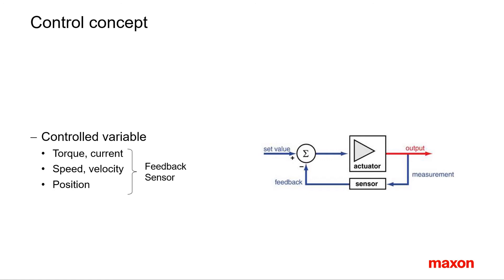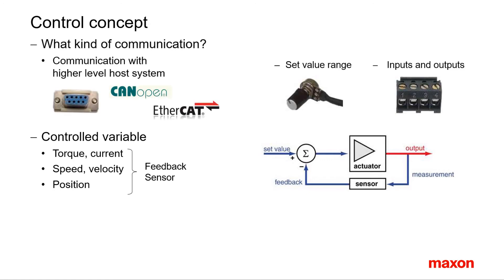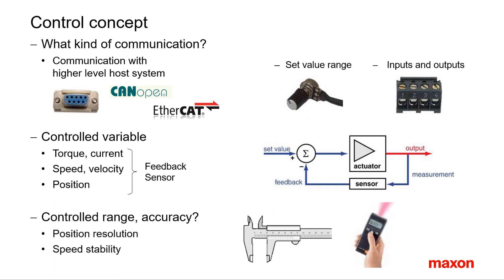Are there additional sensors needed? How is the information passed on to the drive system? Is there a supervisor or master system? If yes, how does this higher-level host system communicate with the drive — for example, via CANopen or another fieldbus, or via a serial interface such as RS-232 or USB? Set values could also simply be given as a digital or analog signal. Do we need additional inputs and outputs — for example, for homing or temperature monitoring? The range and the needed accuracy of the controlled parameter has to be defined.